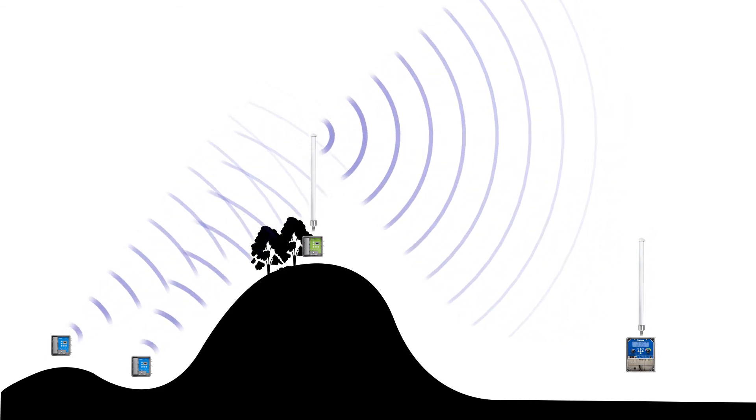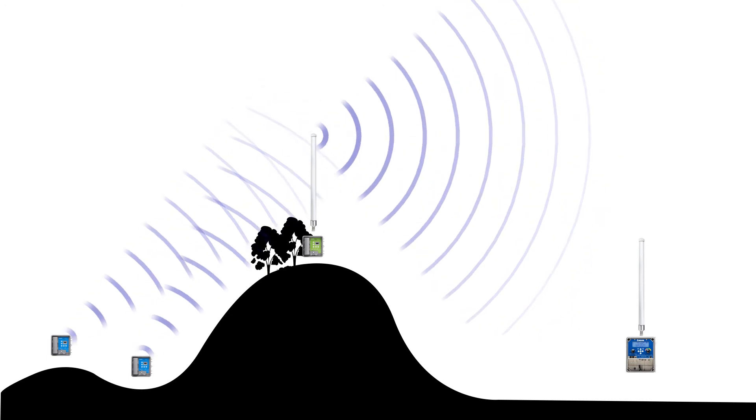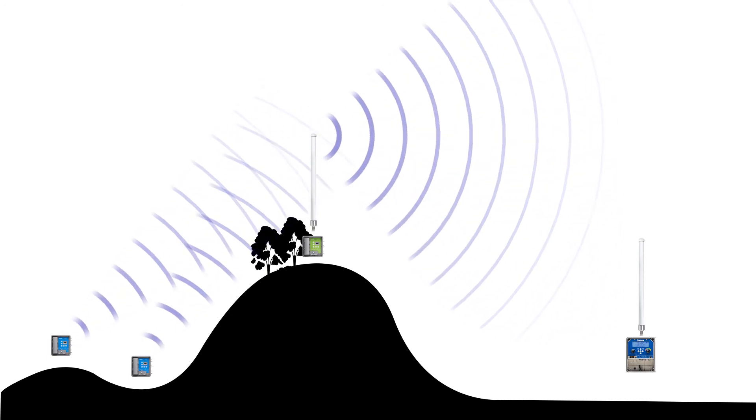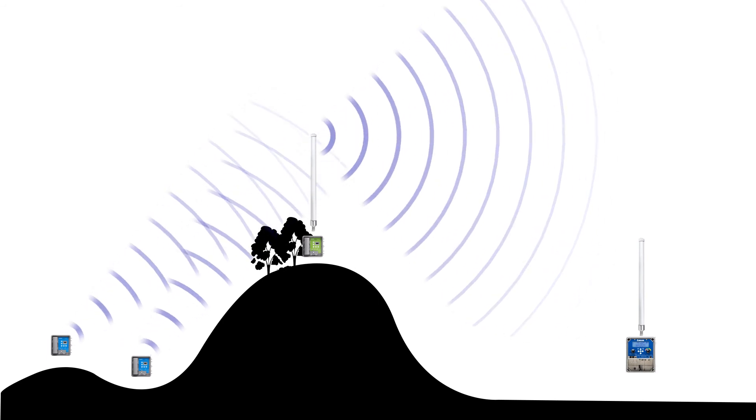The TWIG network can accommodate up to 9 Repeaters. When using more than one Repeater linked in a chain, it is possible for the links to break and could result in the loss of valve control further outward in the chain, so please operate with caution.